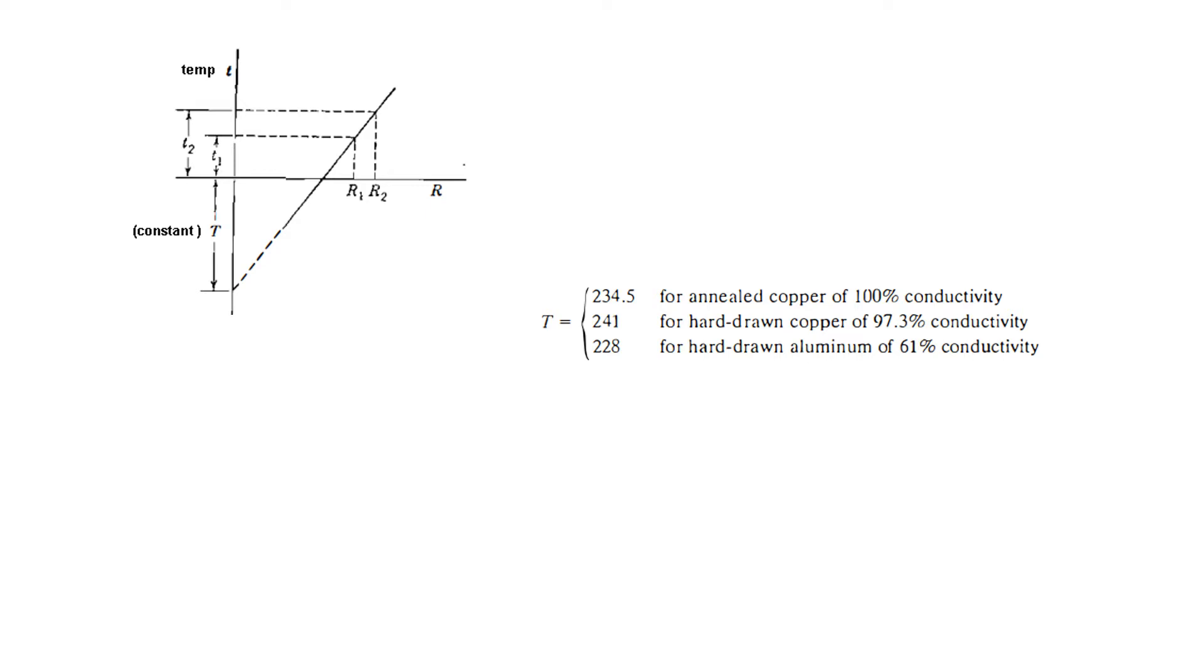The relation between increase in temperature and resistance is shown by this diagram. The easiest way is to keep this formula in mind: ΔR/R = ΔT/T. This capital T is fixed and for hard drawn aluminum it is 228, so in this example we will use 228.